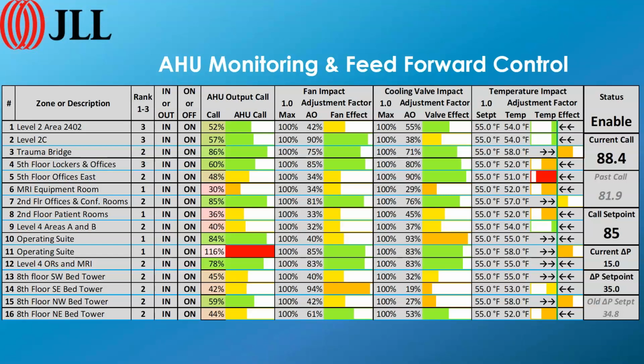And what happens with the delta P control is we make small changes in it, by half a PSI or 3/4 of a PSI. We go up or down and we wait 15 minutes or so until the change in pump pressure has an effect on those air handlers. And we'll make another adjustment, up or down, up or down, up or down. We'll change that set point by a PSI to half a PSI in that range. Just change it up or down slightly and watch that effect on those air handlers and see what we have to do to keep those air handlers satisfied.